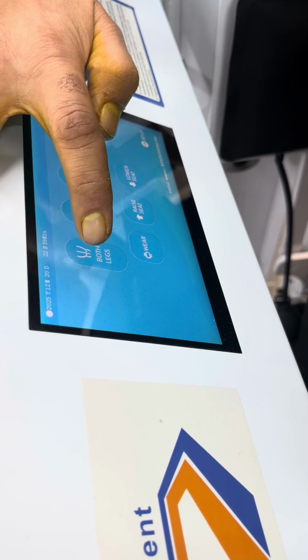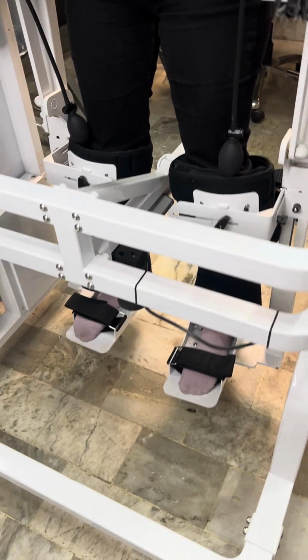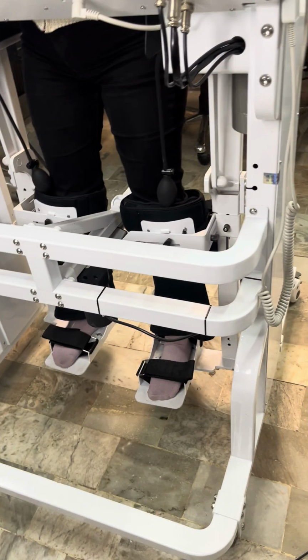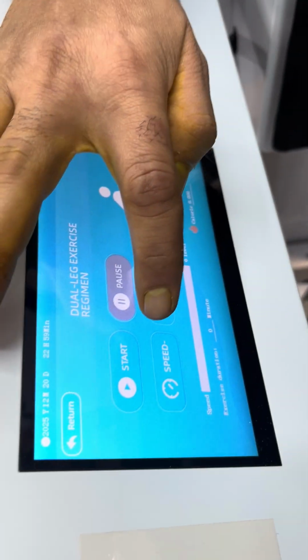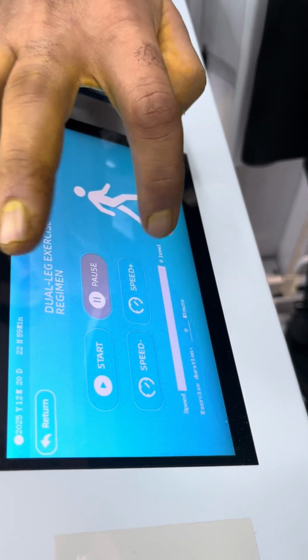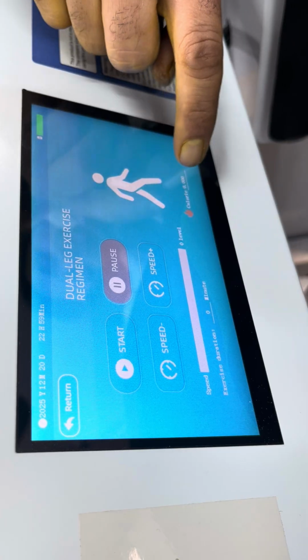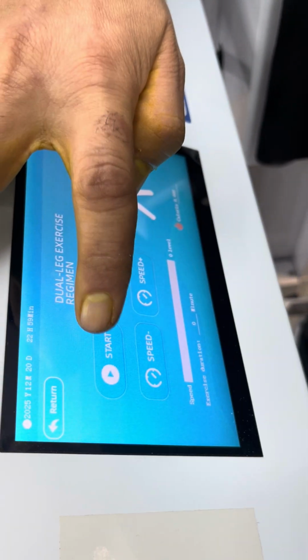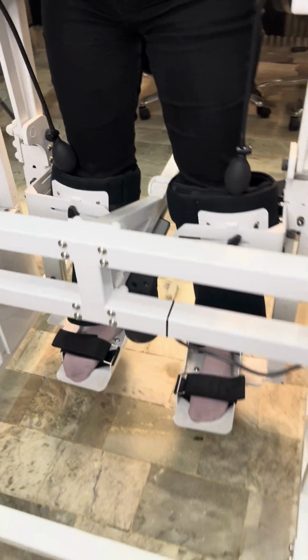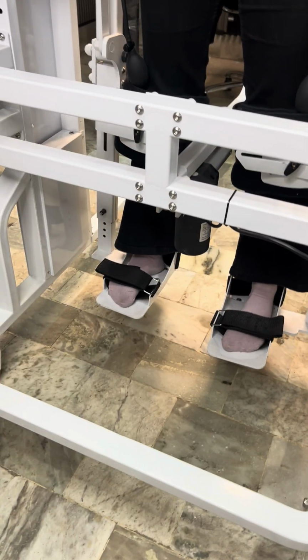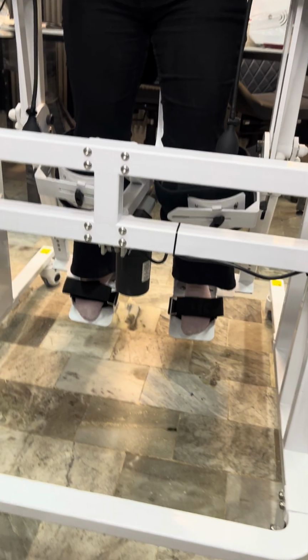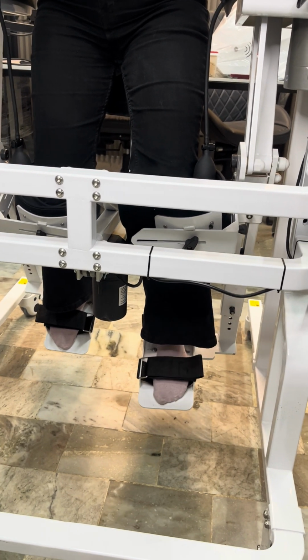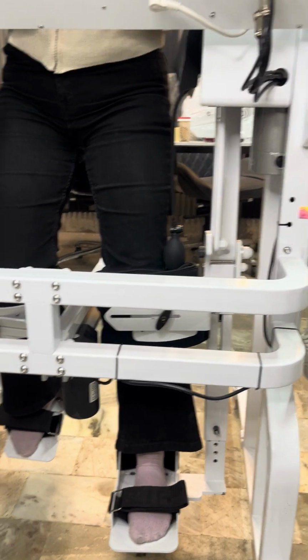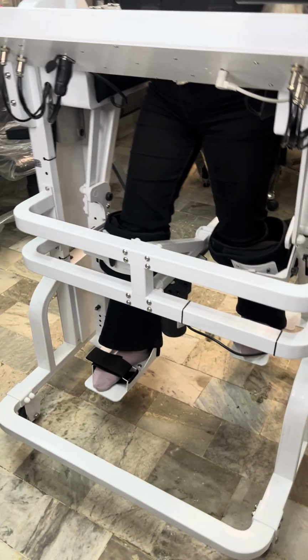So now I will show the same with both legs. So I click on both and confirm the same, and you can see over here that there are 5 levels of speed from 1 to 5, and exercise duration will be shown over here, and calorie also shown. So if I press the start button, the treatment will start. I need to increase the speed. So the start button I have pressed. Now you can see the movement of dual. So you can see this is the dual leg movement.